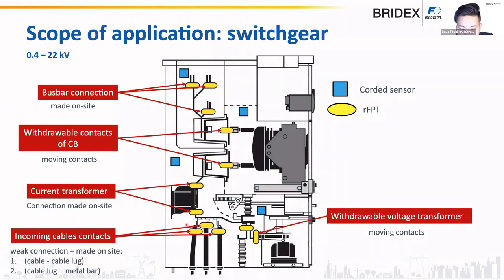The current transformer connections and incoming cable contacts, especially incoming cable contacts, because there are actually 2 connections on this one cable. The first connection is between the cable and the cable lug, where you shrink in the metal part of the cable. And the second connection is between the cable lug and the metal bar here. The cables are also prone to vibration and some shock currents, so we need to ensure that the RFPT is installed there. And for voltage transformers, also because it's withdrawable, it's a moving contact that gets worse and worse with time. And we need to ensure that this connection is under control.